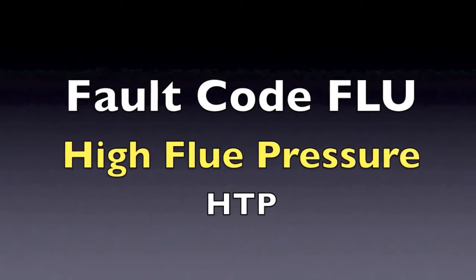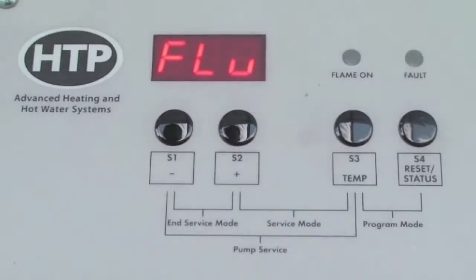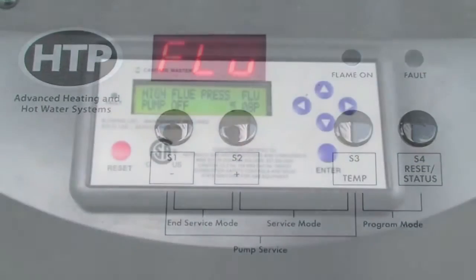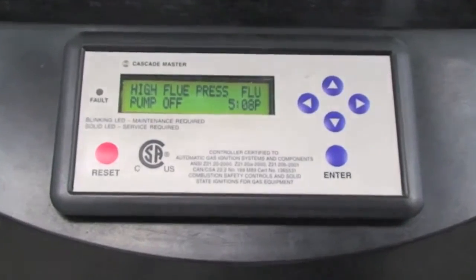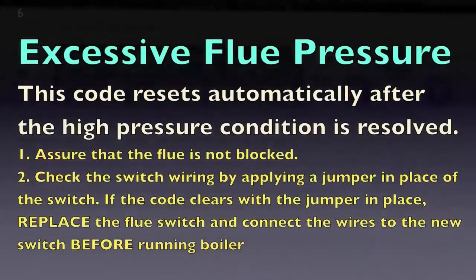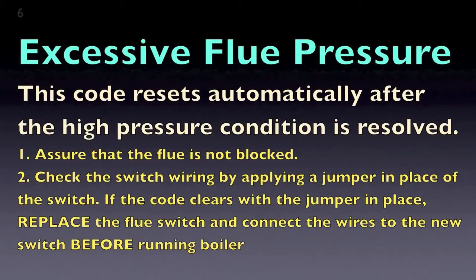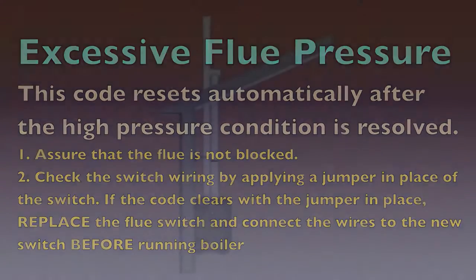If you are getting an FLU in the display, this indicates that there is excessive pressure in the exhaust vent. The switch is normally closed and opens when it sees pressure in the exhaust vent above an inch and a half water column. The unit will reset after 90 seconds to see if the blockage has been corrected.